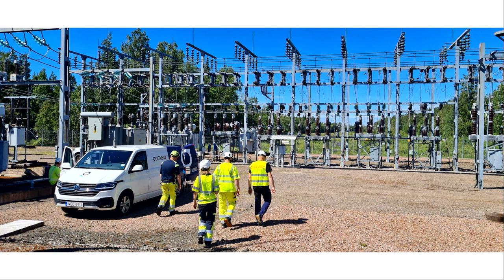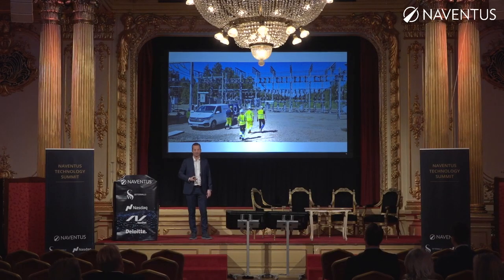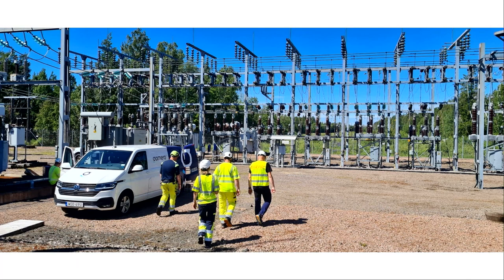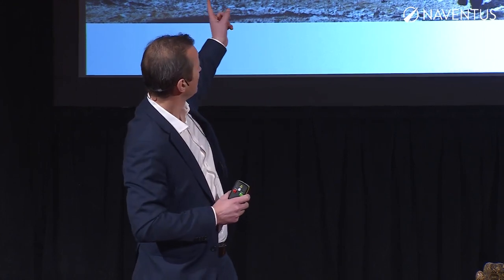So now we're working with Ellevio to connect more equipment out on the substation. Here we have a specific project, we are going to connect all these circuit breakers here. Circuit breakers, to create a non-flammable environment, you use SF6 gas, a very good gas for that, but it's very harmful, more than 20,000 times more harmful for the environment than CO2. And it's expensive, so they need to make sure that the SF6 gas is always there and that the pressure is right.